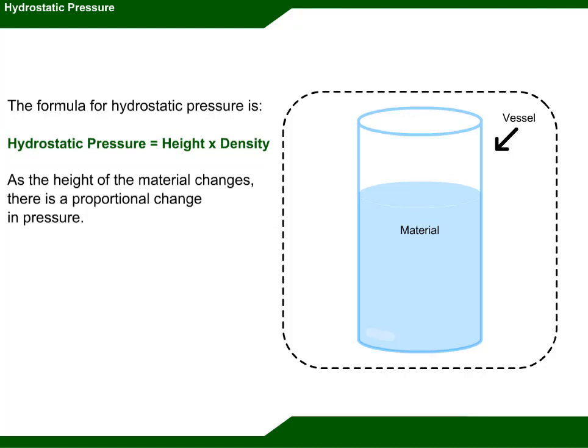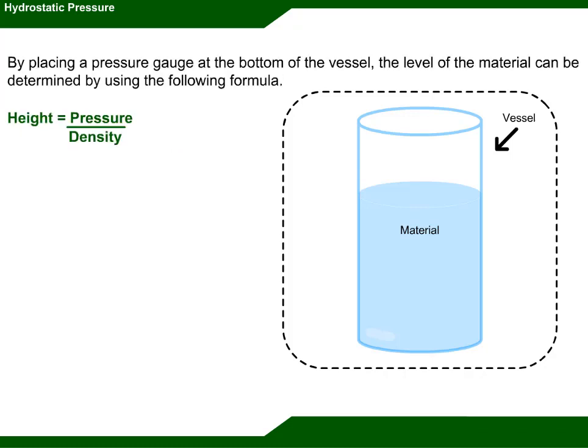As the height of the material changes, there is a proportional change in pressure. By placing a pressure gauge at the bottom of the vessel, the level of the material can be determined by using the following formula: height equals pressure divided by density.